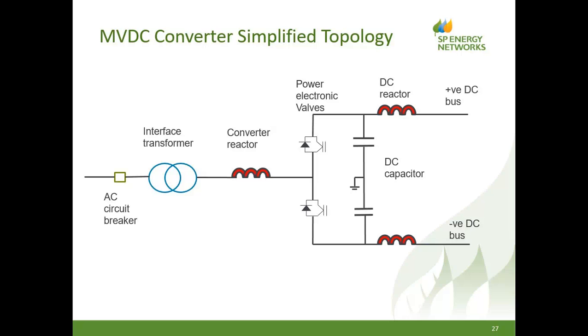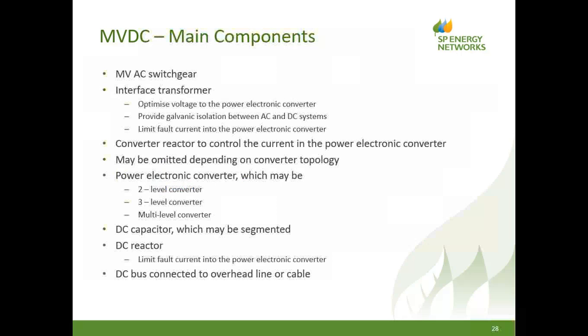If you go to the next slide, I'll just run through some of these key features. The AC switchgear is standard medium voltage switchgear, nothing special. The interface transformer essentially gives us three functionalities. It optimizes the voltage in the power electronic converter. It does provide very important galvanic isolation between the AC and DC systems.